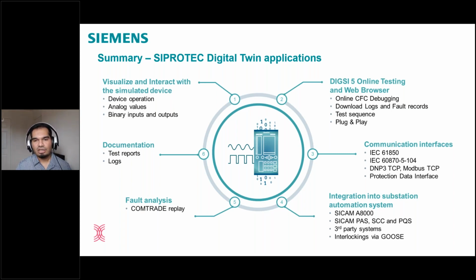Then let's go to the communication interfaces. We support 61850, 104, DNP3 TCP, Modbus TCP, and protection data interface. What this means is that you can also have inter-relay communications. Both of them can be on the cloud, or you can have a physical relay communicating to the relay on the cloud using a VPN bridge, or you can have the relay in the cloud communicate to a SCADA system, which is on your PC, again by using VPN, or you can have it communicate to an RTU by using a VPN bridge. So multiple possibilities are available using this digital twin application.